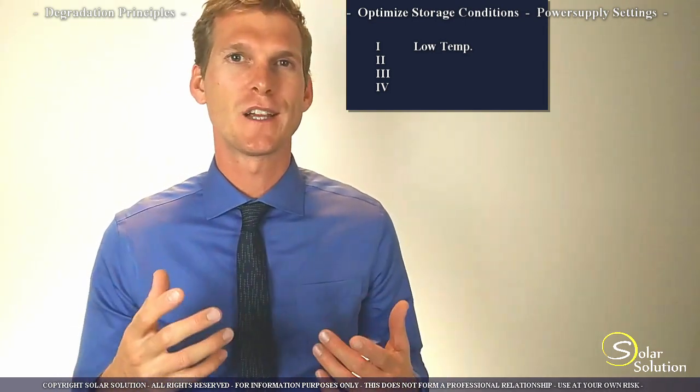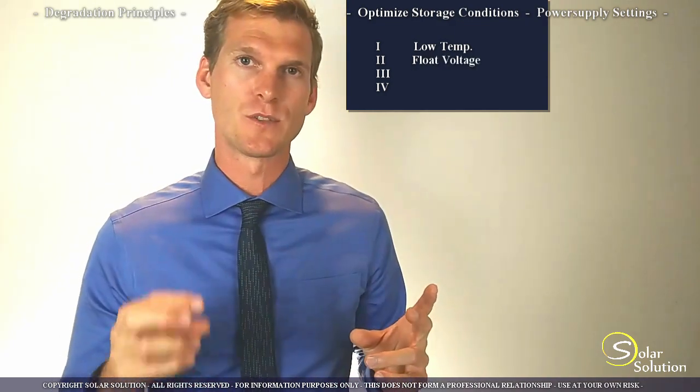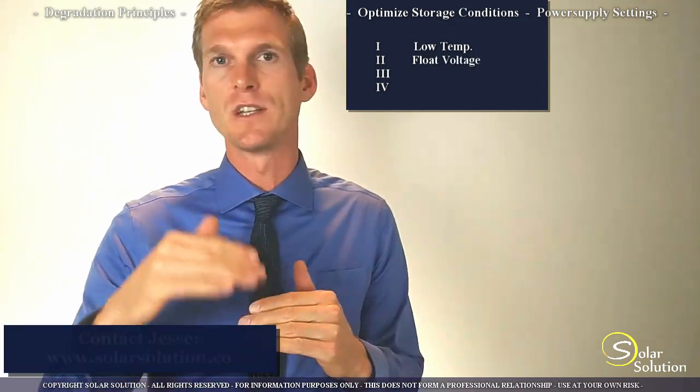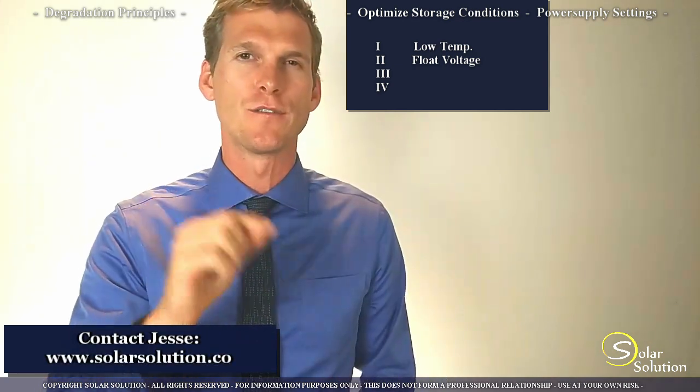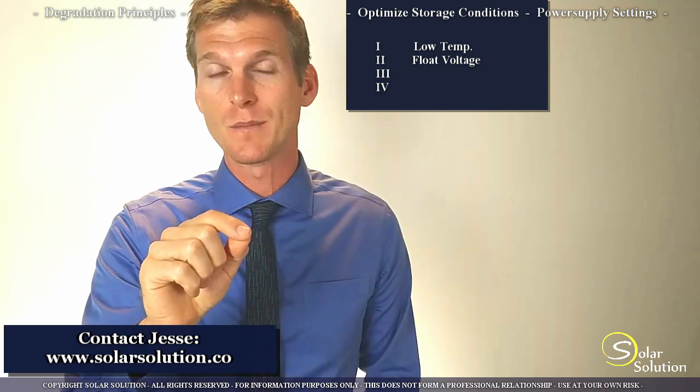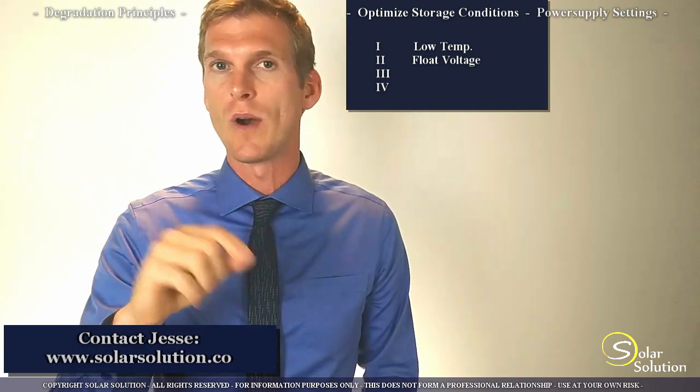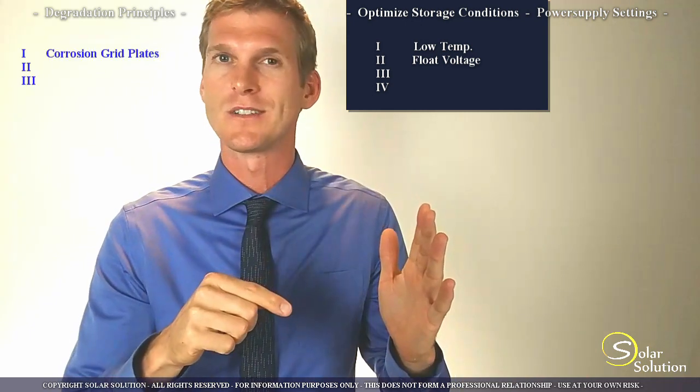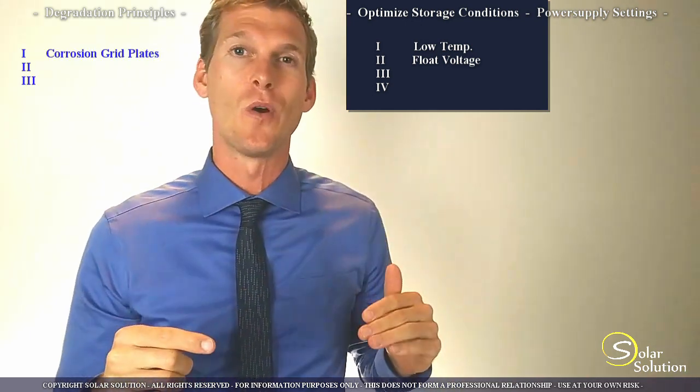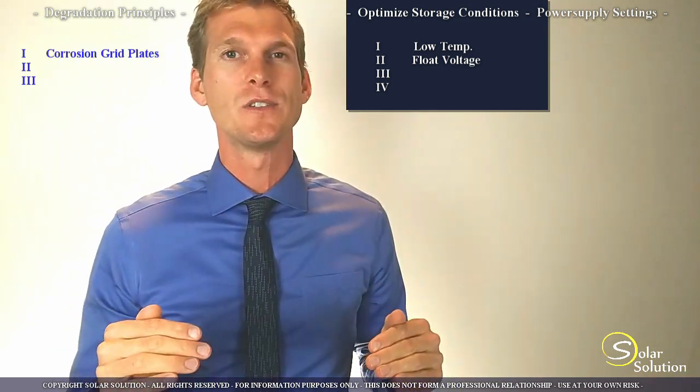Now another very simple but very effective thing you can do is setting the right float voltage for your system. So the float voltage is the voltage at which the battery will be kept if it's 100% charged. So you can find the right value for your specific battery in a specification sheet or ask your supplier. Now if you keep the float voltage too high you will cause excessive corrosion on the positive grid plates. Remember we discussed that before. If you set it too low you're actually undercharging your battery and you can cause excessive sulfation on your battery.